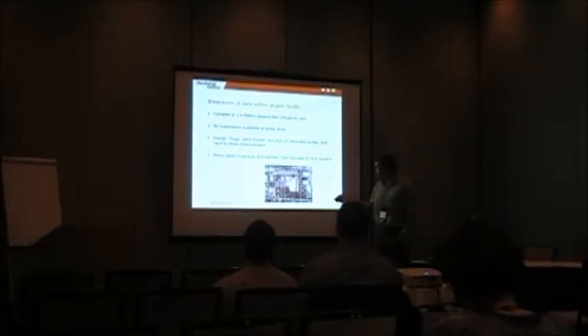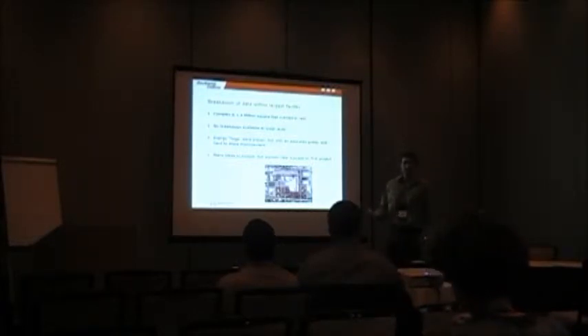The problem was we could not get any data below the site level of detail. We could see usage every five minutes, but it only told you the usage of the whole facility in five minutes. So we asked, where is that data coming from and what's the biggest breakdown? We didn't have any information below that level. So go find the opportunity in 1.4 million square feet to reduce energy — you don't even know where to start. We had ideas about key equipment but it was really just a guess, and without any baseline it's hard to show improvement. So we wanted to be very structured about how we went after it.